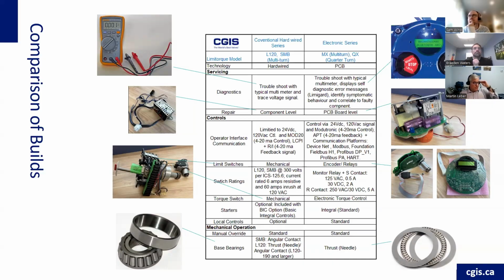So what's the beauty of each of these? The nice part on the conventional actuator that uses a contactor like this, you just need a multimeter and you can troubleshoot it. Think of the guys out in the field at 2 in the morning with a problem. We're not saying Limitorque actuators break, but every actuator has a problem at some point, particularly after running a long time with no maintenance.